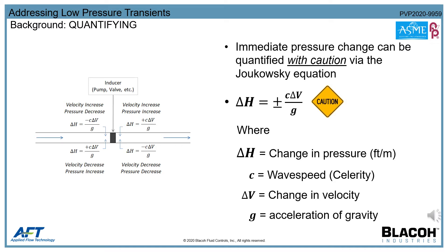The opposite is true when the pump shuts down: the fluid velocity decreases, causing a high pressure transient at the inlet and a low pressure transient at the outlet of the pump. The reason for caution when using the Joukowsky equation is that it is not always the worst case pressure circumstance. It can capture the initial pressure change, but computer surge simulation software becomes necessary once transient pressure waves begin superimposing upon themselves, or when other events such as line pack and cavitation occur.